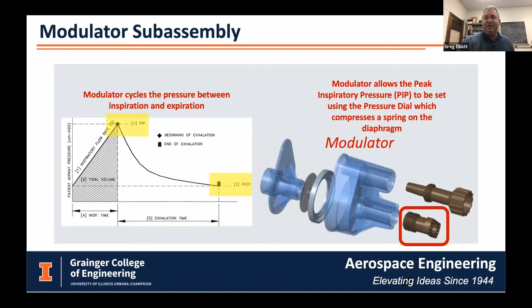You can see the two knobs that are there, which allow you to set the pressure and also the rate of the breathing cycle. It was interesting to me how this device actually could work. Basically, in this modulator, we designed it so that the tube that came from the manometer and was attached to the patient, and also the incoming oxygen, would pressurize. You can see that little green disc there, which would start to be pressurized inside that tube. As that's being pressurized, the patient is going through an inhalation cycle.